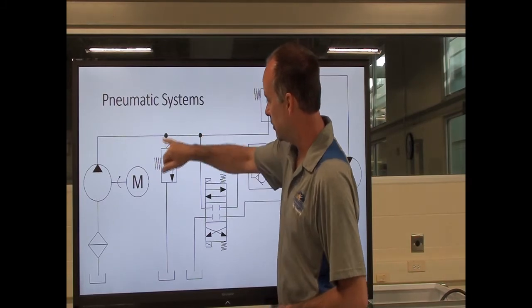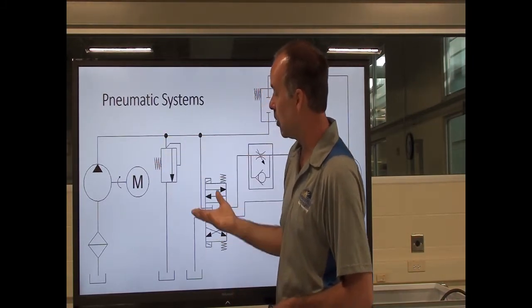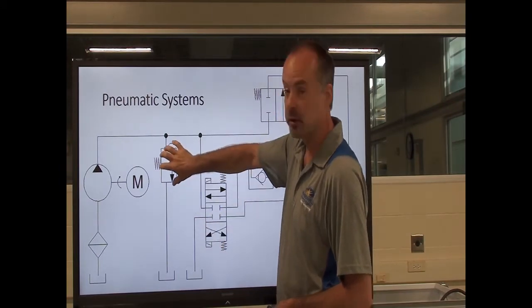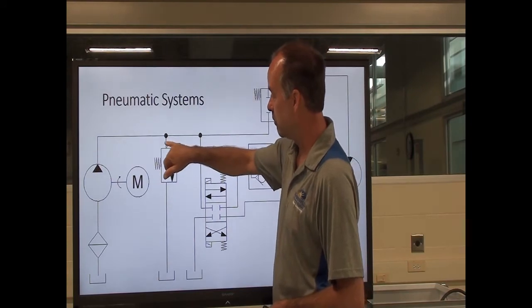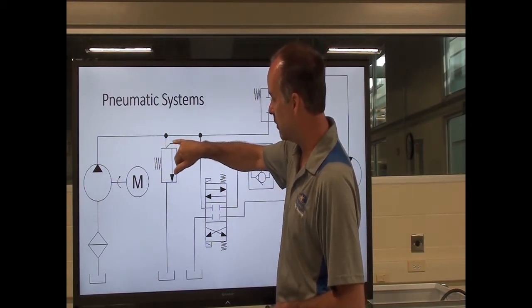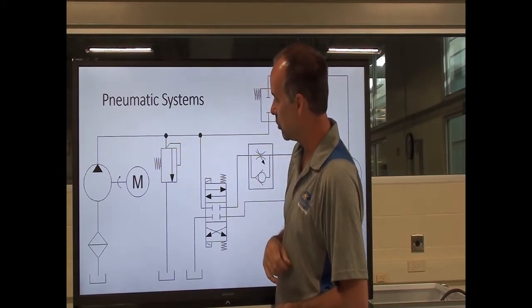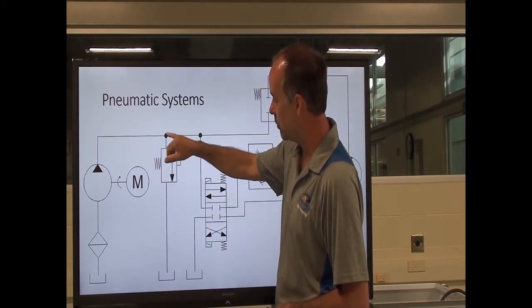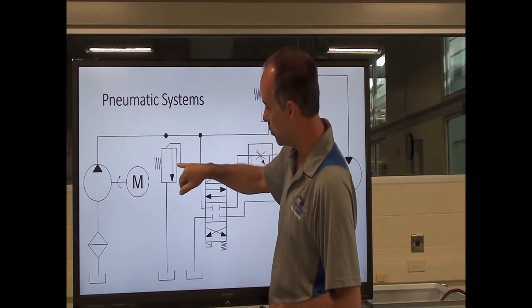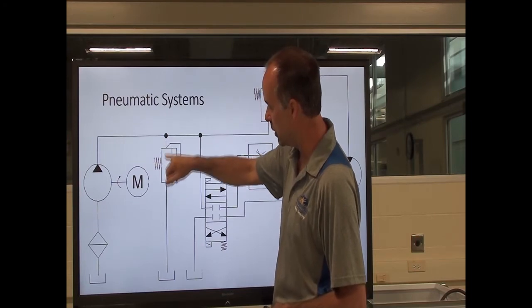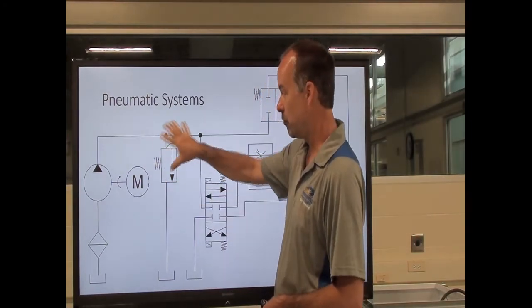These dots show that these lines are connected. The first component we come to is a pressure relief valve. I can identify this as a pressure relief valve because my pilot port is coming off the input side of the valve, acting on the internal spool against the spring. So when the system builds enough pressure, the pilot port will shift the spool against the spring and allow fluid to drain, thus maintaining the overall system pressure.